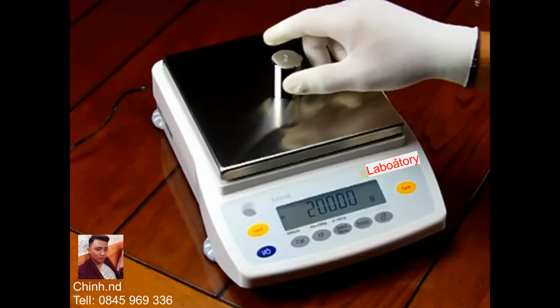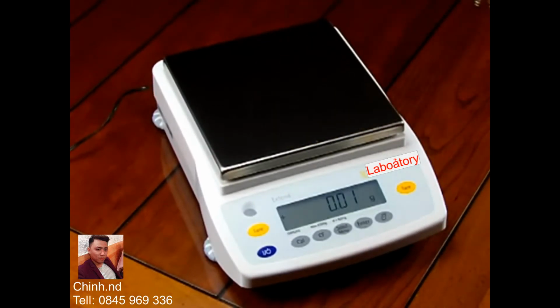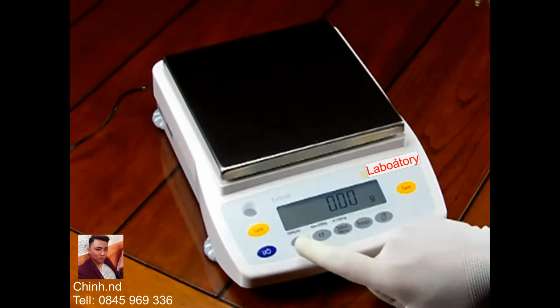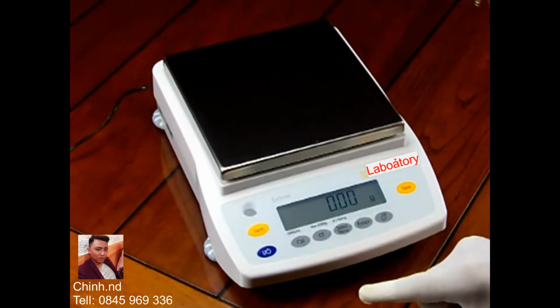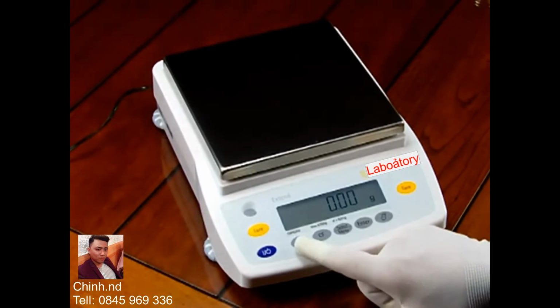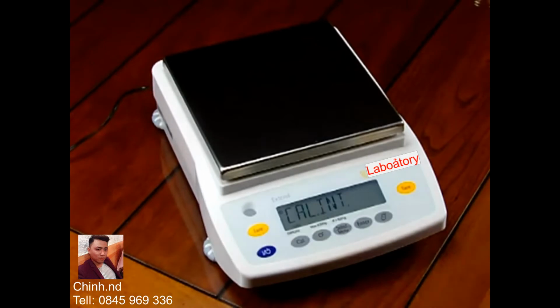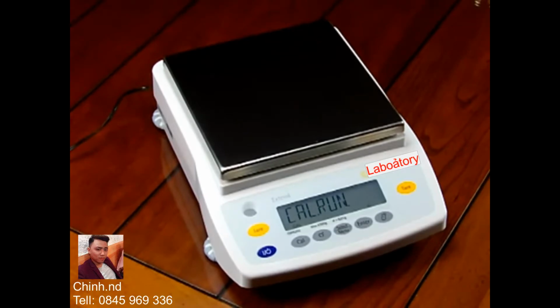Another feature that this balance has to offer, the Sartorius GW6202, is internal calibration. Now you can calibrate this balance both externally and internally, but calibration is achieved simply by pressing the cal button, and you'll notice, if I'm quiet, you'll hear the little servo motor running, and it's dropping the calibration weight and performing calibration.